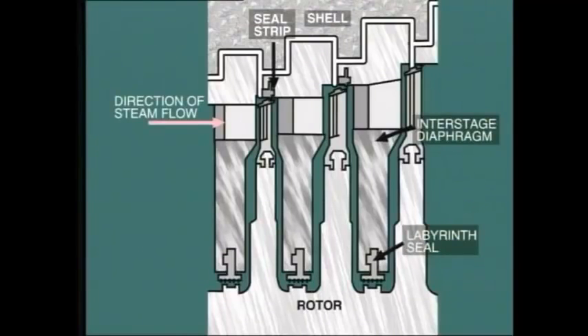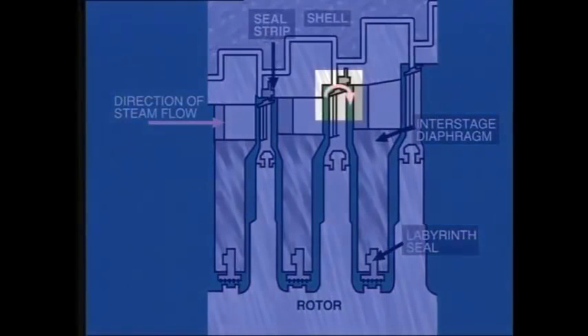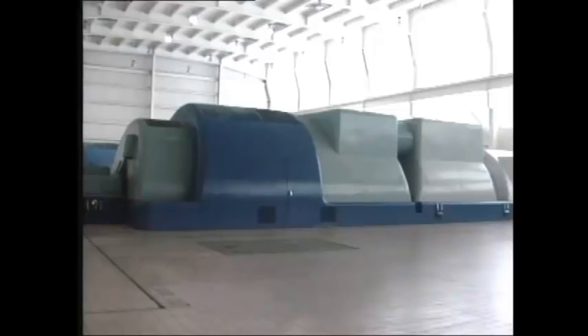Although the reaction turbine is efficient in its use of heat, there is always the potential for some losses due to steam leaking around the periphery of the moving blades, especially in the high-pressure section. In order to reduce this tendency, a reaction turbine will normally have many more stages so that the pressure drop in each stage is lower. Consequently, the machine will be physically longer.